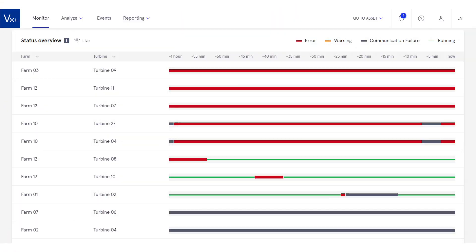What they're doing with clustering the turbines is fascinating because what they're trying to accomplish is what a lot of people in the industry want — tell me which of my turbines in a wind farm might need to be taken down, or could be taken offline at the same time to have maintenance scheduled. If you can monitor several turbines seeing largely the same loading and damage accumulation, the clustering in this data analytics platform can help you determine that six turbines are coming up to a time frame in about three months where there's a high probability of catastrophic failure. You then take those turbines offline before that happens — whether it's a lubrication change in the gearbox, gear damage, or something to do with the blades — enabling predictive maintenance scheduling that minimizes AEP loss.